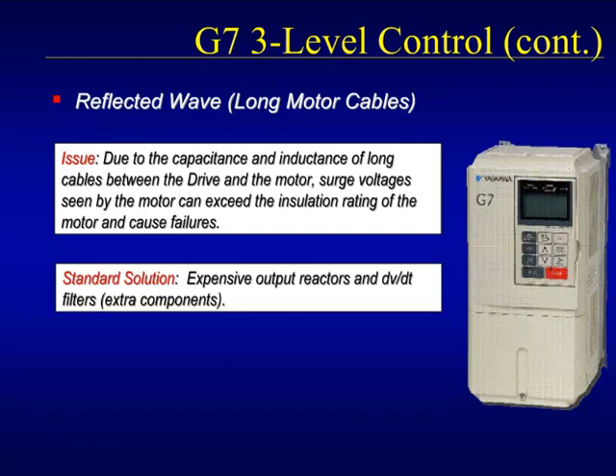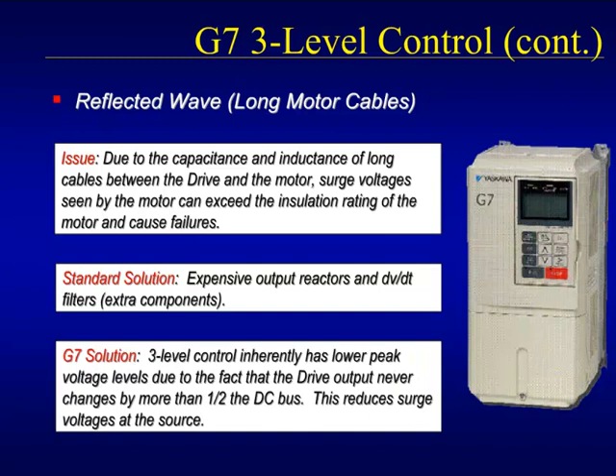In the past, the only solution to the problem of reflected wave was to add costly output reactors or dV/dt filters. The G7 drive's 3-level control greatly reduces the effect of high dV/dt by outputting the voltage pulses in steps, which in turn suppresses the surge voltages seen by the motor windings without the need of any external equipment.